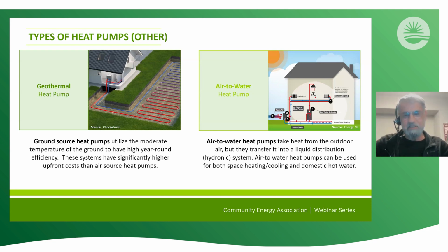Yeah. No, that's absolutely correct. They're quite expensive, and they don't have the life cycle payback they used to, because there was a time when air source heat pumps were much less efficient. However, the technology of air source heat pumps has come to the point where they're no less efficient than ground source heat pumps nowadays. So with ground source heat pumps, you're really paying a premium for about the same value when it comes to operating efficiency.